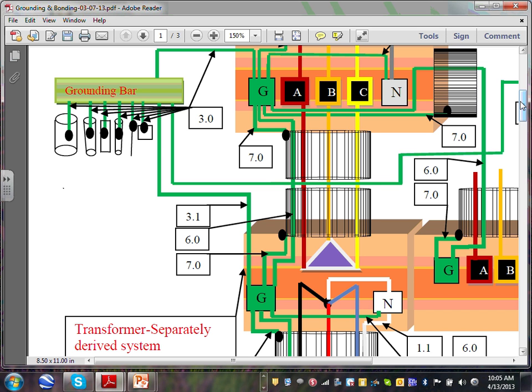As far as this panel is concerned, this is a load, and it needs an equipment ground conductor, right? So now looking at the high voltage side of a transformer, you need the same thing, guys. Can you see that wire coming here? That could be the same wire. Tie the flex on both sides, here and here, and go through it. Tie this piece of equipment to this piece of equipment. It does exactly the same thing as this piece of wire, except it's sized differently.